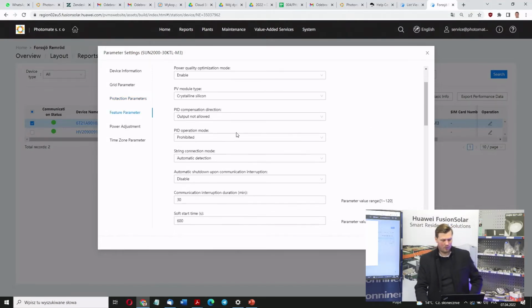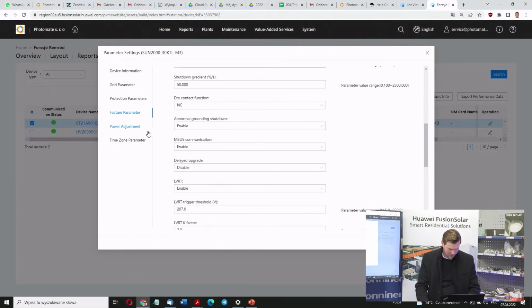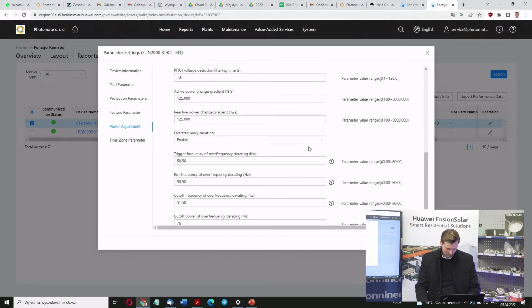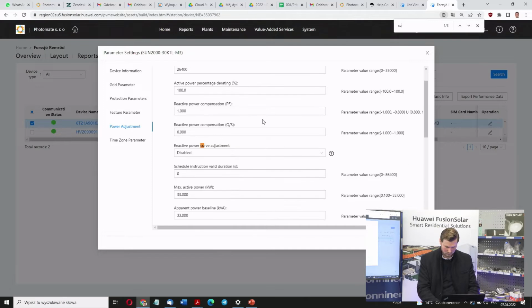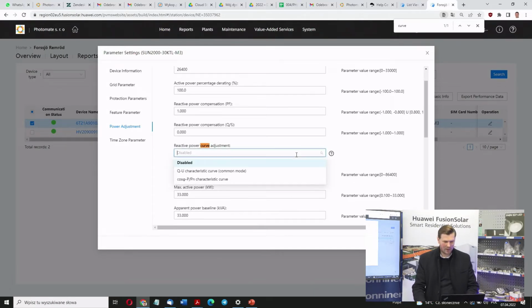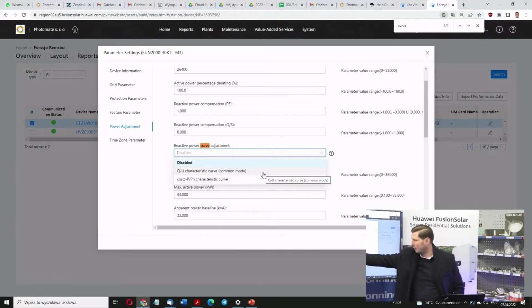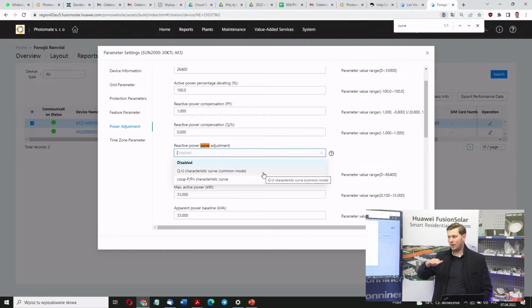For example, there's a very nice function, let me check this. Okay, so just an example of what you can do remotely to solve a problem with grid overvoltage: you can change the characteristic curve output of the inverter, so it will compensate the output voltage with some reactive power. This can be set based on output power - when the inverter power reaches a limit like 50%, it changes the power factor, meaning the inverter will compensate the output voltage of the system by a few volts, which might solve your problem remotely. It's very good to know this option is available here.